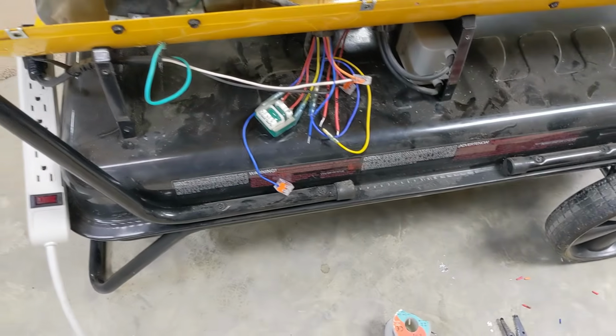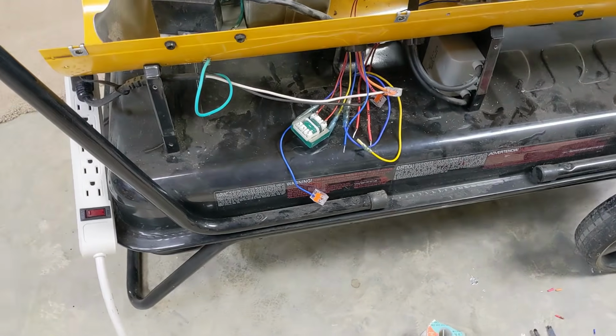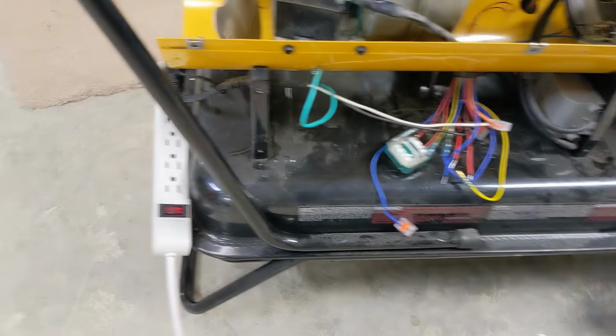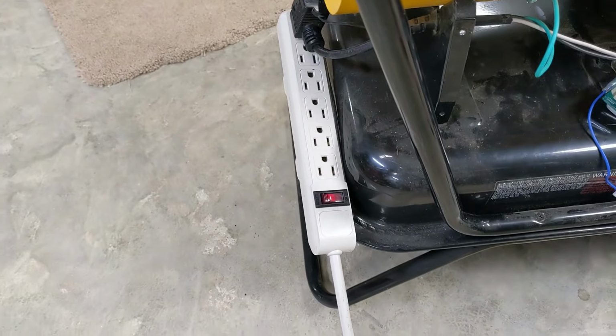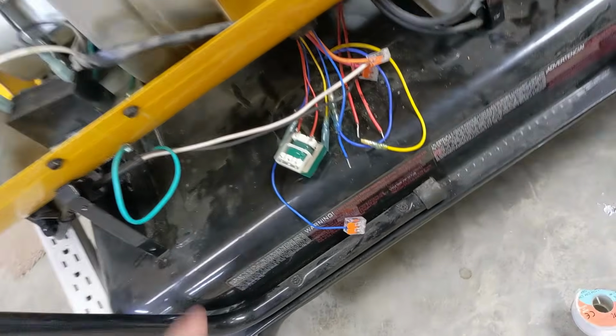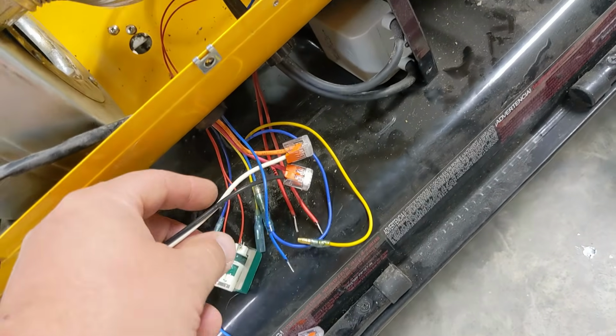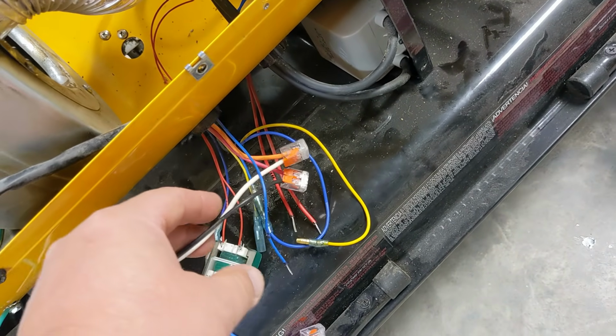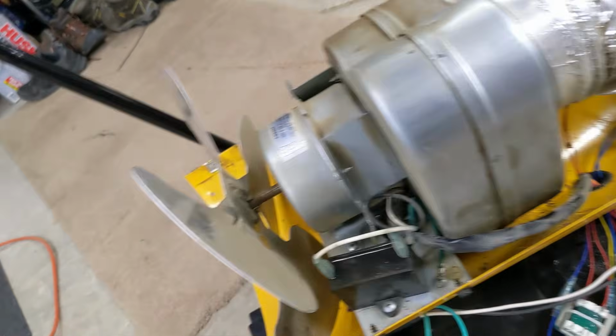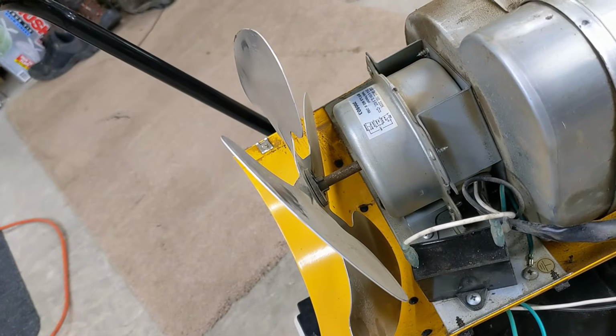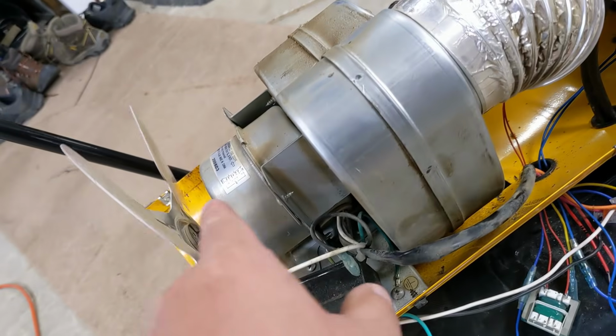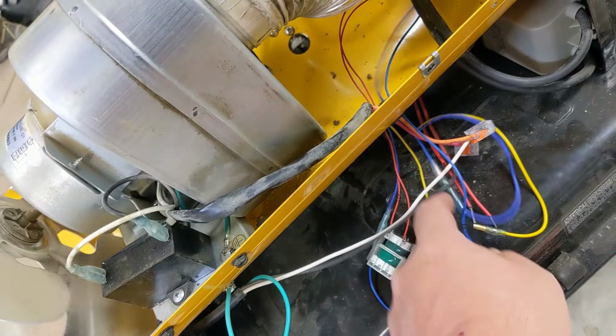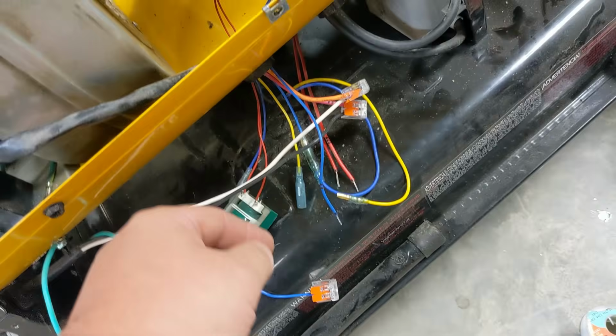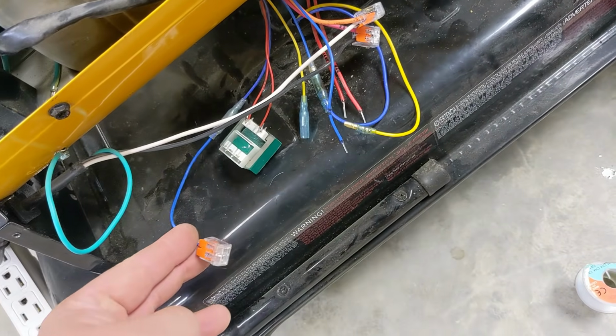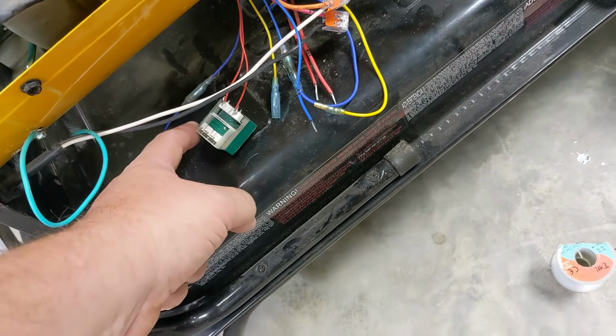Just to make sure I'm not crazy, what I decided to do is test each individual system. I've got power coming in on the power strip, it's turned off at the moment but the mains come in. All I've got it tied to is the blower motor. Yellow and blue come out of the same connections but they are disconnected. There's the yellow, isolated and insulated, and there's the blue. So nothing's gonna short out.